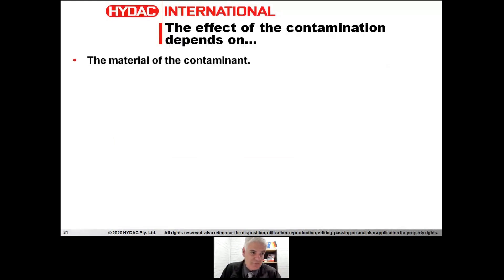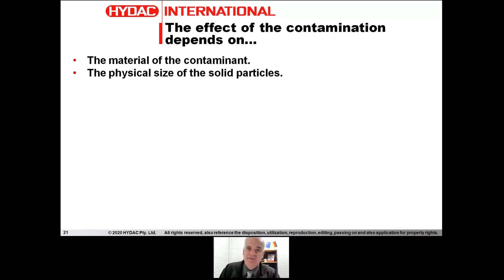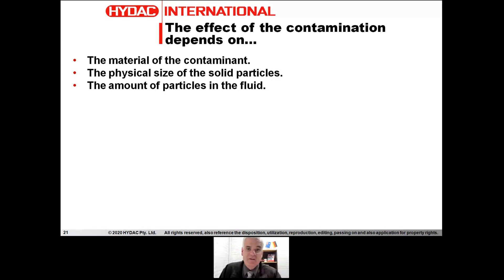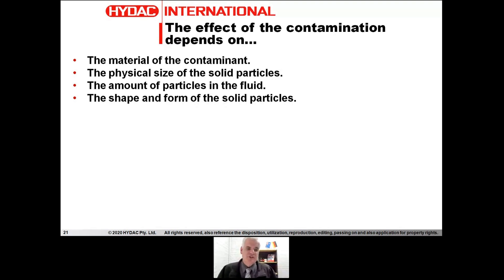Not every contaminant is going to be as damaging as another one. The material of the contaminant is very important. Other things that make a difference are the physical size of those solid particles — the larger they are, the more damage they can do, but larger particles sometimes don't get caught between running clearances, so medium-sized particles can be very damaging as well. The amount of particles in the fluid also matters clearly — the more you have, the more damaging it's going to be. The shape and form of solid particles makes a difference too.